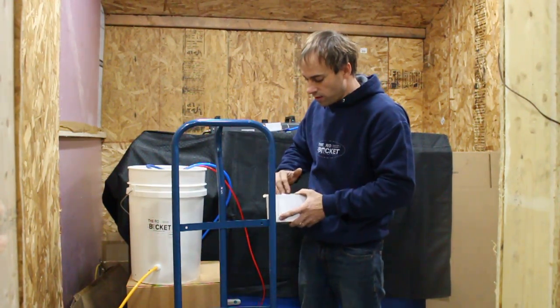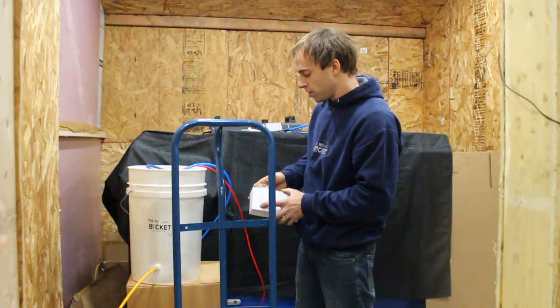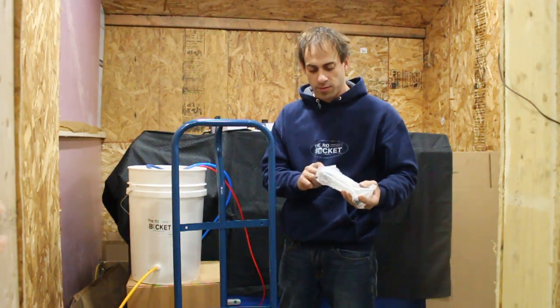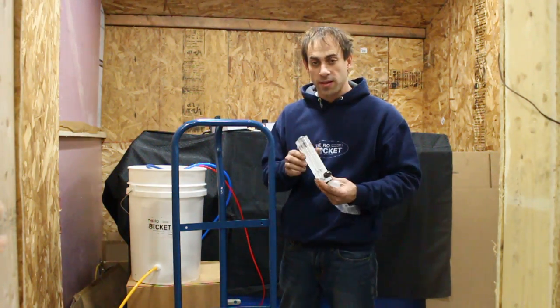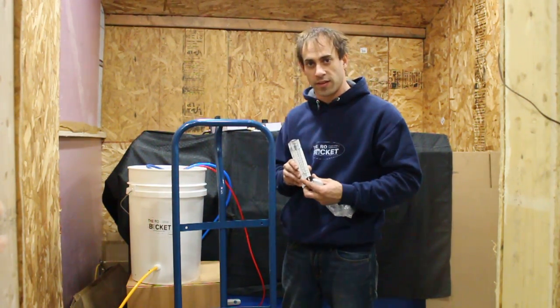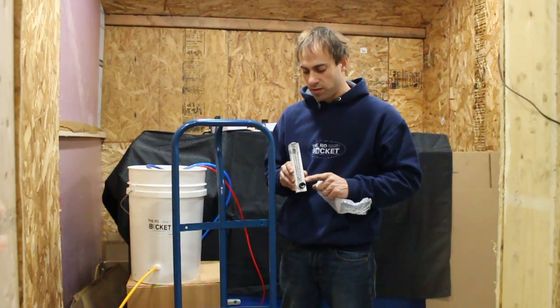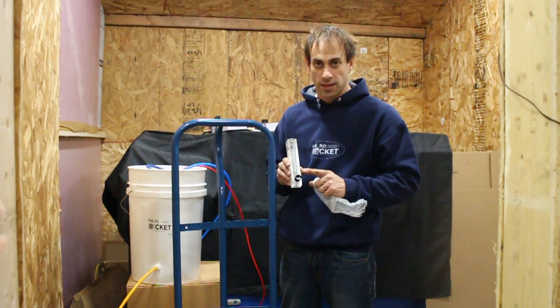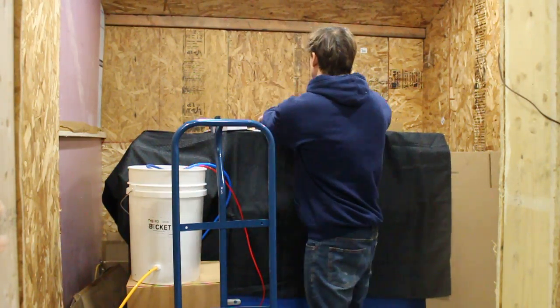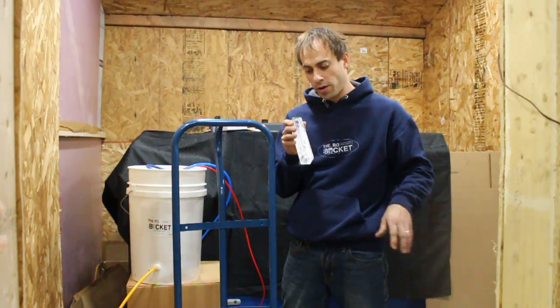So when you buy this, it's going to come with two meters and a couple pieces of hose. When you buy the set for the bucket or RB20-25 set, one of the meters is going to have a needle valve built into it. This is going to be in place of the current needle valve on your system, so you're not going to use the existing needle valve once you use this meter set. You're going to use the built-in needle valve on the concentrate meter. The other meter is just a plain meter with no valve.